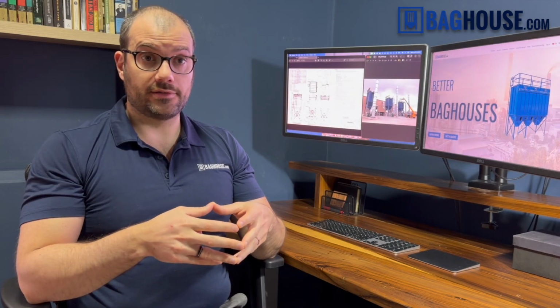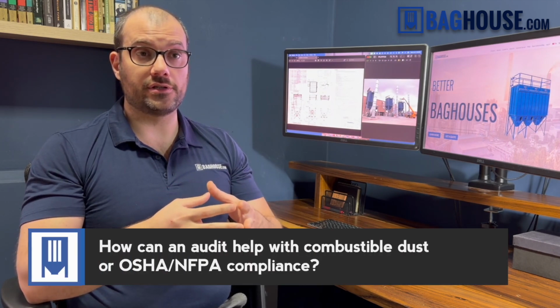For a lot of customers, one of the biggest benefits of our system audits is that it lets us bring to their attention deficiencies with regards to safety when it comes to OSHA, but also combustible dust hazards as it relates to the NFPA standards or maybe insurance requirements for combustible dust. Many times we go to a facility, if they have combustible dust, they're usually aware of it already when we come. So it's not usually that we discover anything new there, but a lot of times plants have incomplete protection strategies in place. And I say incomplete with regards to what's required by NFPA standards or the local fire marshal, for example, or incomplete in the sense of not providing full optimal protection for protecting their equipment. In either case, whatever the main reason is you want to upgrade things, our system audits will identify that.